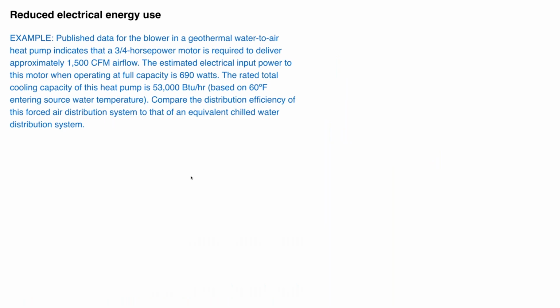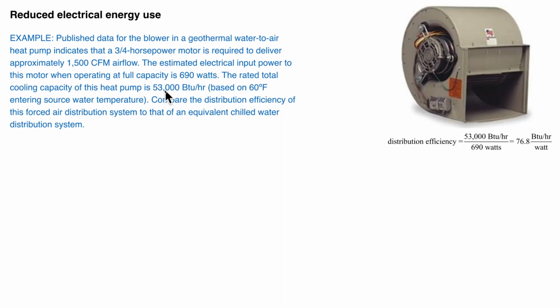Now, I want to talk about distribution efficiency, just to give you a comparison. I took some data for a geothermal water-to-air heat pump. Water-to-air meaning the water side is connected to a geothermal loop, and we're using some type of ducted forced air delivery system. In that particular unit, a 4.5-ton rated unit, it had a 3/4 horsepower motor, and it was delivering about 1,500 CFM. At full capacity, that motor was requiring about 690 watts of electrical input to deliver 53,000 BTUs per hour of cooling. And if you want to get the distribution efficiency over here, let me just move some things around so I can see it.